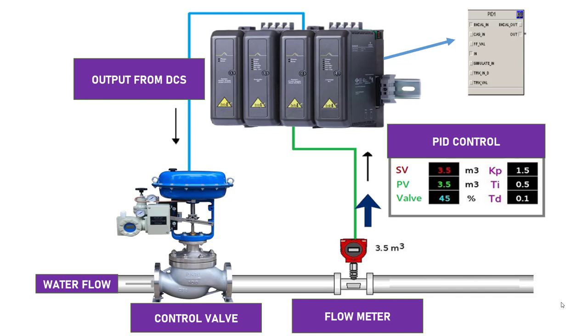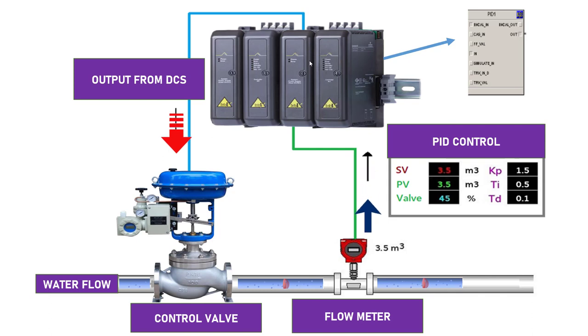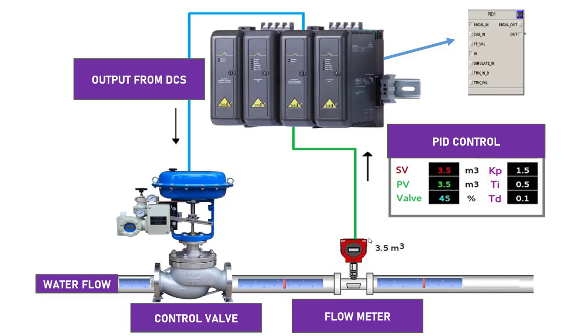In this video, we are going to understand how to write a code to control a control valve using PID in DeltaV DCS. Before writing a control program, it's important to understand the control loop. In this example, water enters a pipeline, a control valve regulates the flow, and a flow meter measures it. The flow meter is connected to the analog input card of a DeltaV DCS, which connects to the controller.